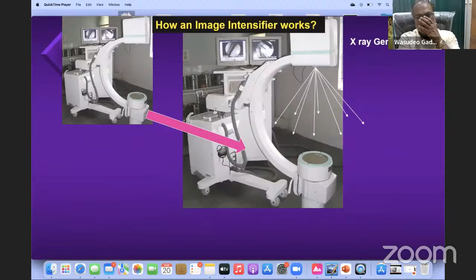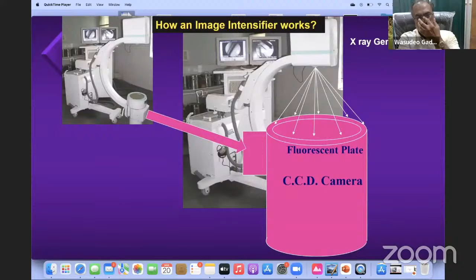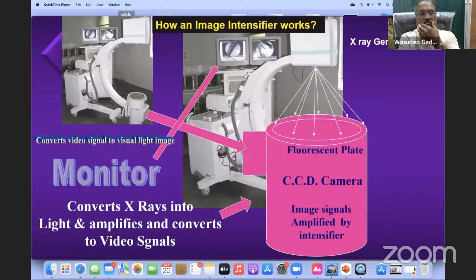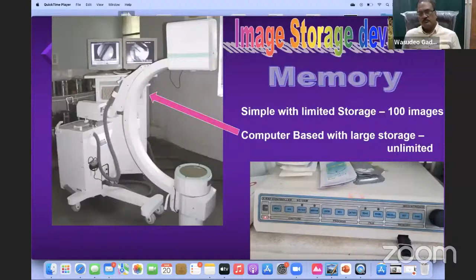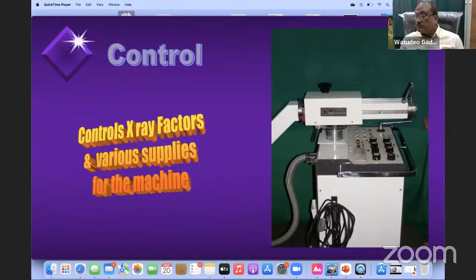How a C-arm works. There is an X-ray generating unit which generates the X-rays, and the II or the image intensifier has a fluorescent plate on which, when the X-ray falls, the image glows and the CCD camera captures it, and it is intensified by the intensifier and converted into video signals, and on the monitor we see the picture. There are two types of storage. A simple storage which can store about 100 images, and a better one is computer-based storage. You can save all the images. There are basic controls over the body of the C-arm. One should know all the switches there.